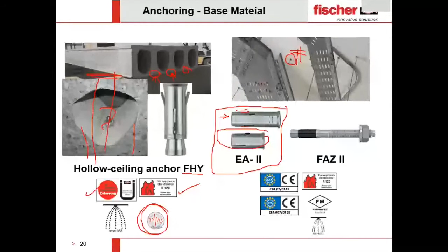Imagine this drop-in anchor with an outer diameter of 10 or 12 mm. You drill exactly the same diameter, 12 mm, then install the anchor. If a crack appears in the concrete near the anchor, the hole may no longer be 12 mm but 12.3 mm, while the anchor's outer diameter stays the same at 12 mm. So what happens? Simply, the anchor can fail.